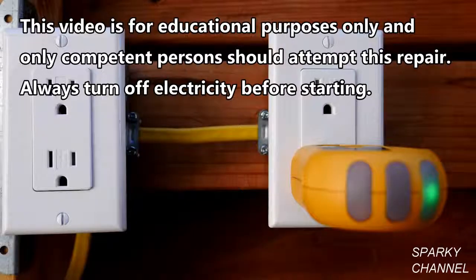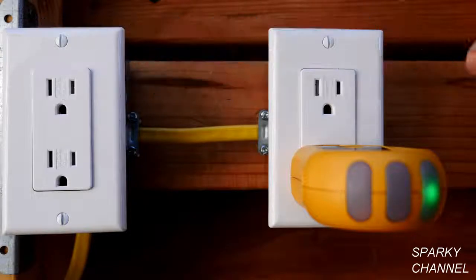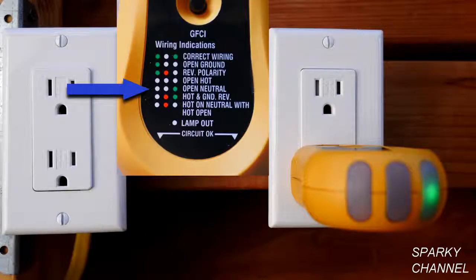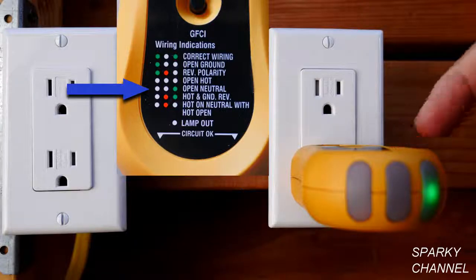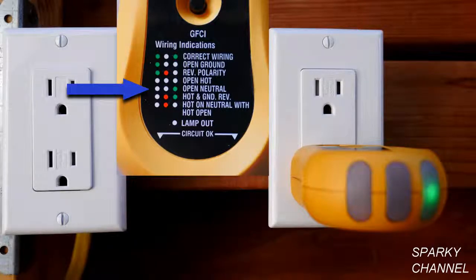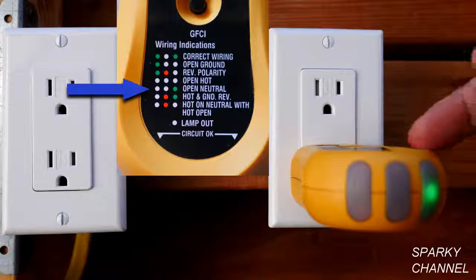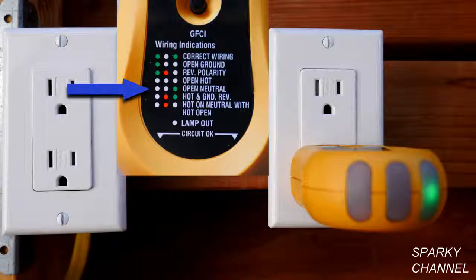Today I'm going to show you how to fix a receptacle that is not working. This is a receptacle that is not working. So what I've done, and what I suggested you do right away, is plug an outlet tester like this one into the outlet. And you see right here there's an index, and check what you have as far as a light. We have one green light on the right here, and check it against the index, and the index says open neutral. So our problem is open neutral.